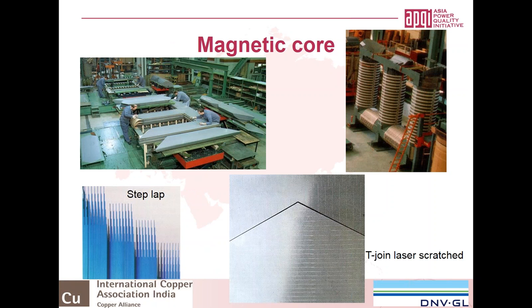If you look at the magnetic circuit, how it is made, and I have this kind of pictures which are the huge transformer, you will see that on the left upper side people are making the core of the transformer. It is made of thin sheets which should be well put together to make the total core. Sometimes you will see that people do it automatically, they have robots doing it, but for the larger transformer normally it's done manually. And in case you ask me why a transformer is in most cases expensive, it's mainly because you have a lot of material in it, but also it's a lot of labor force which is needed to manufacture a transformer.